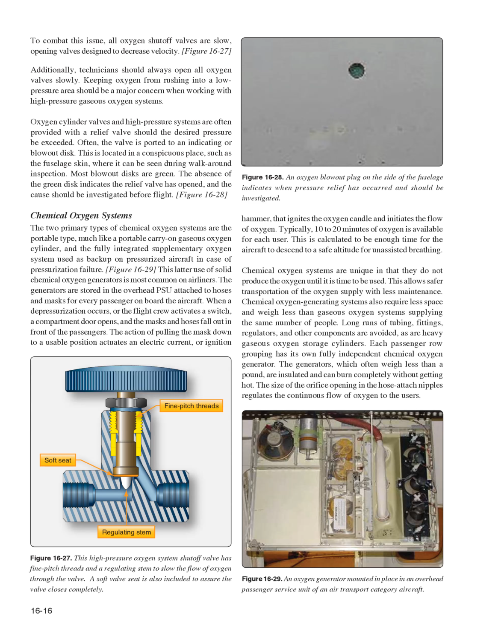To combat this issue, all oxygen shutoff valves are slow opening valves designed to decrease velocity. Figure 16-27: additionally, technicians should always open all oxygen valves slowly. Keeping oxygen from rushing into a low-pressure area should be a major concern when working with high-pressure gaseous oxygen systems. Oxygen cylinder valves in high-pressure systems are often provided with a relief valve should the desired pressure be exceeded.